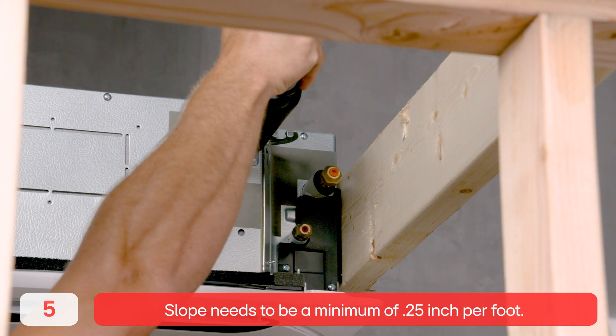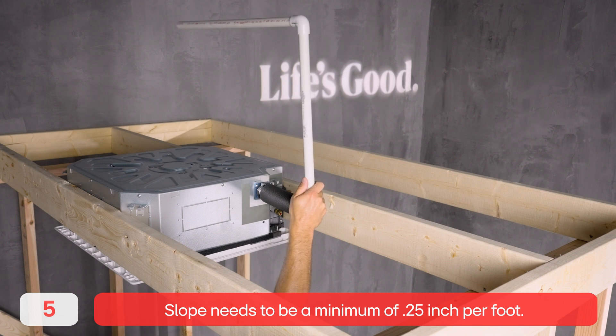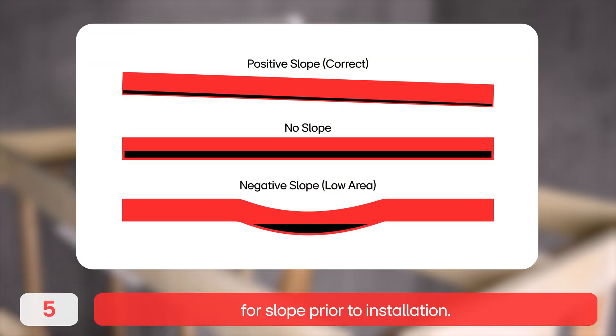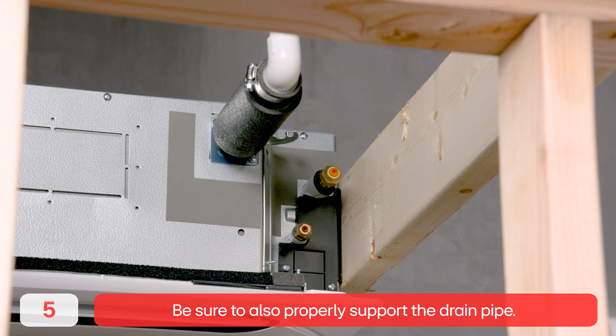Slope needs to be a minimum of 1/4 inch per foot, but you should also check the local and national requirements for slope prior to installation. Be sure to also properly support the drain pipe.